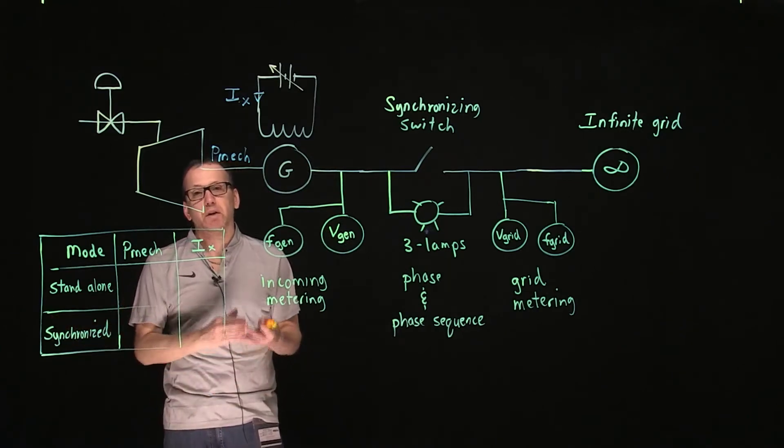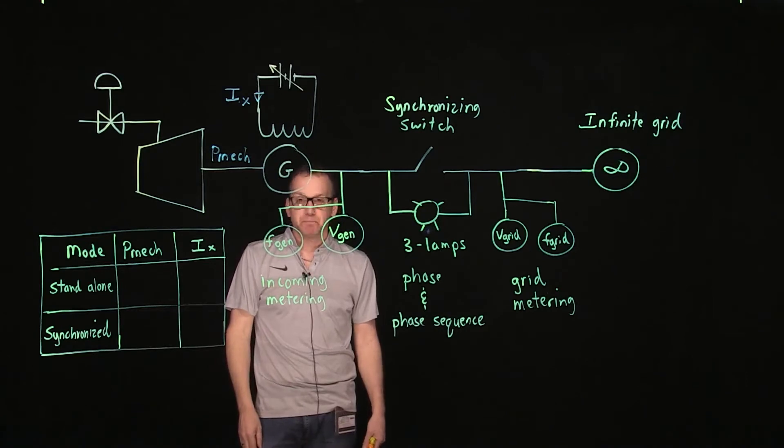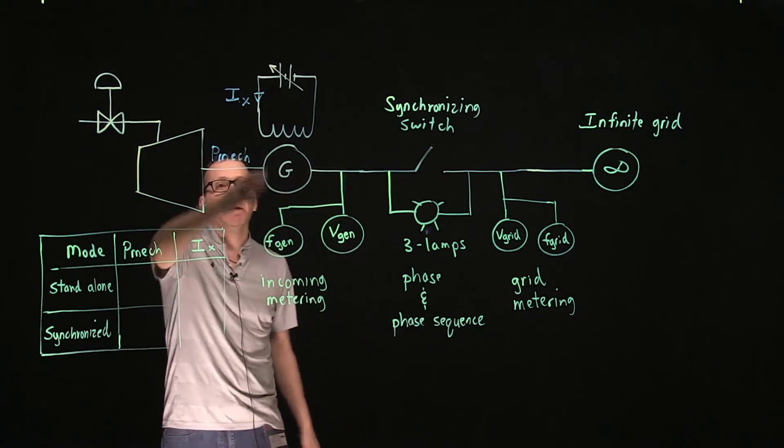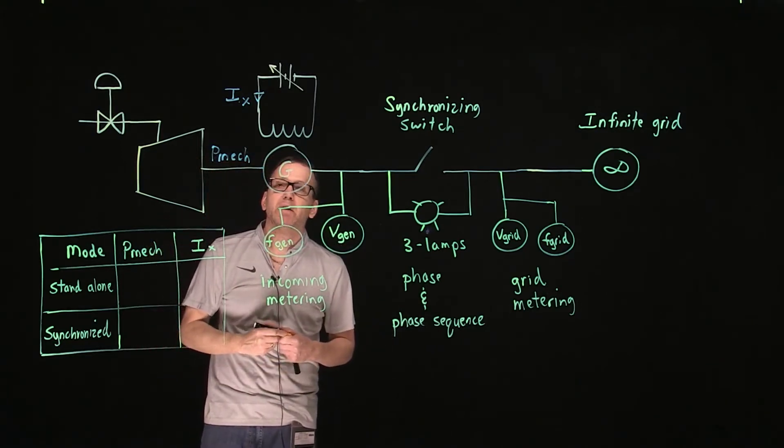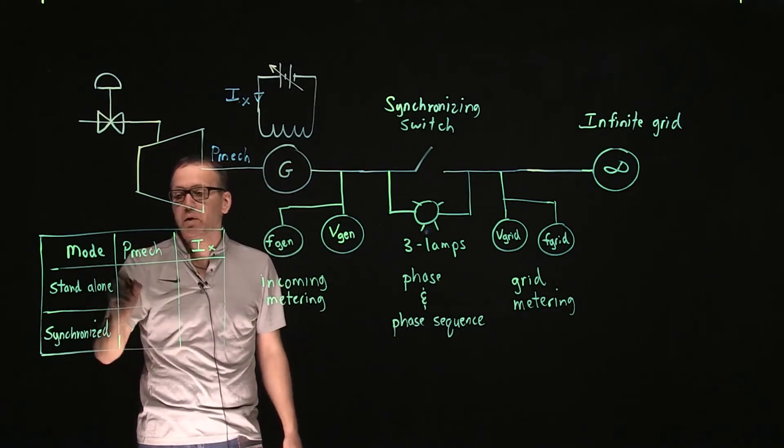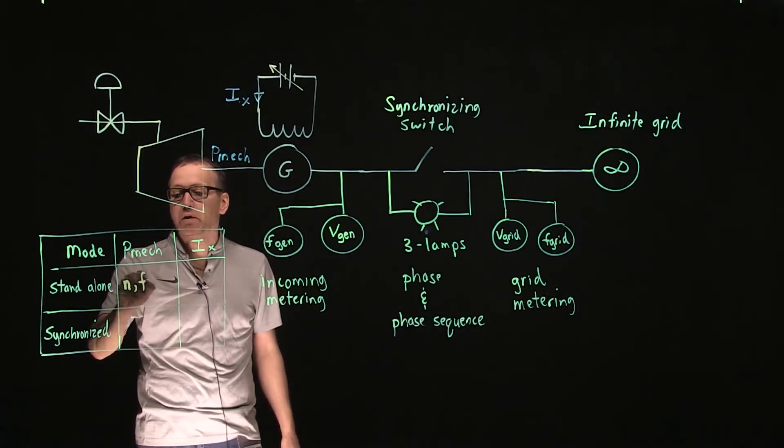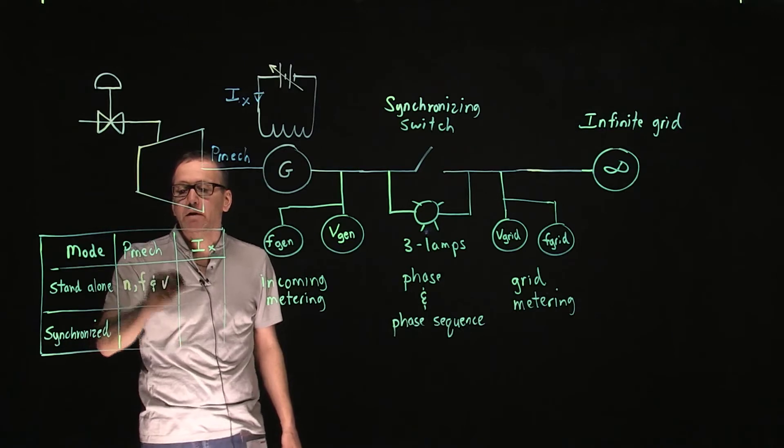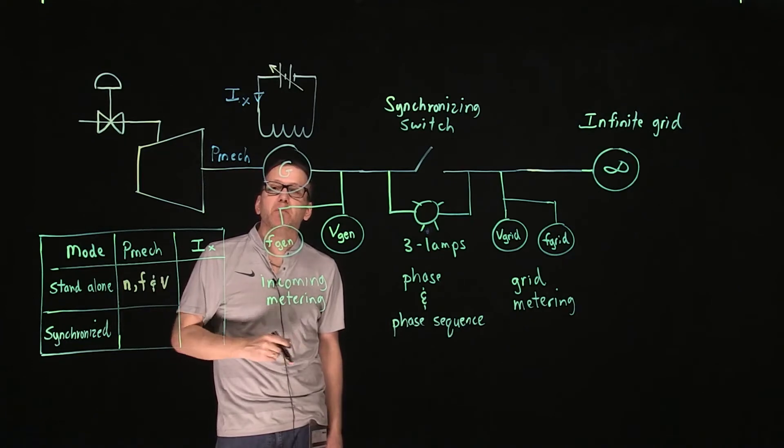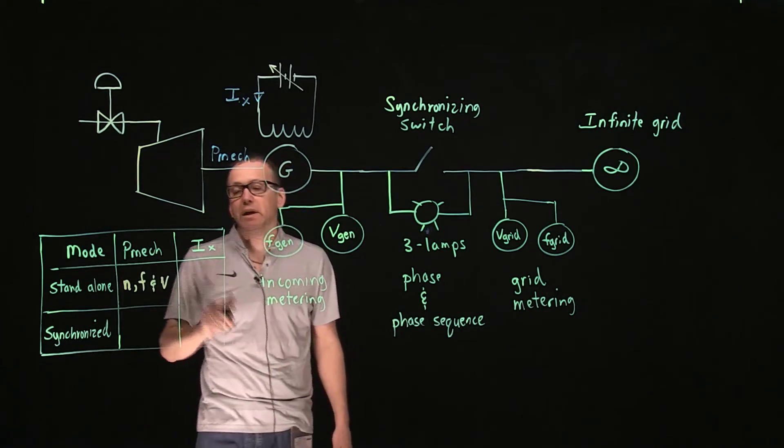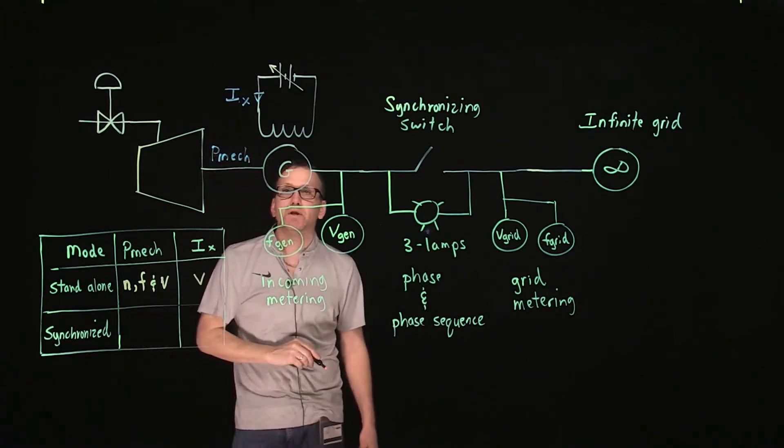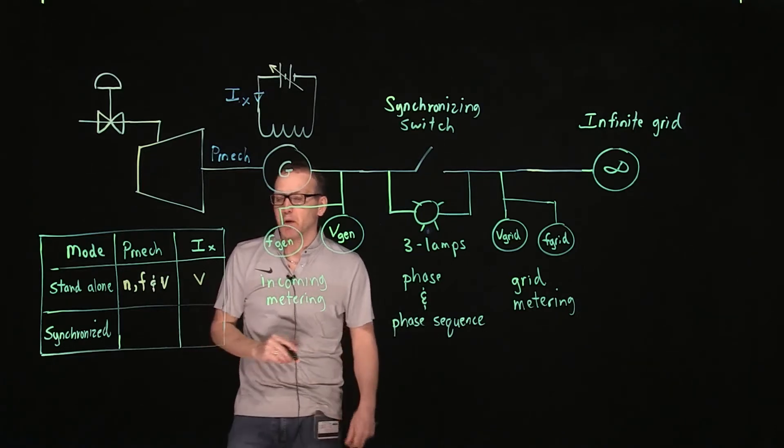In standalone mode, we observed that the mechanical power input to the generator from the turbine, or in our case the prime mover, affects the speed, frequency, and output voltage. That's what adjusting the mechanical power on the shaft of the generator does. The excitation current can only control the voltage output of the generator.